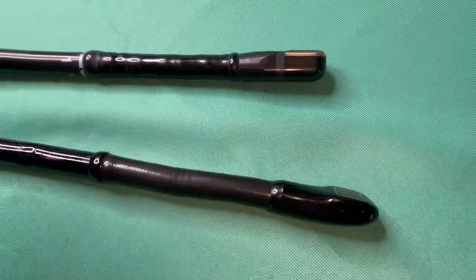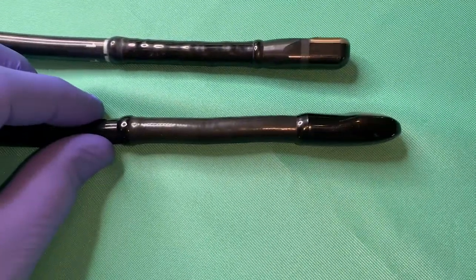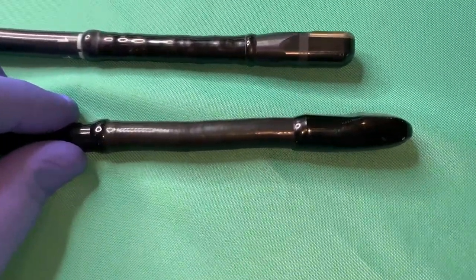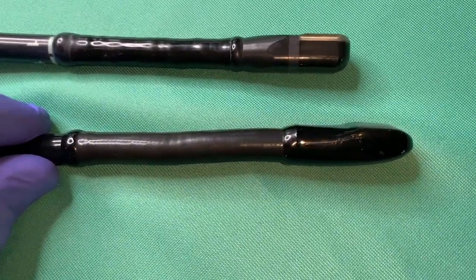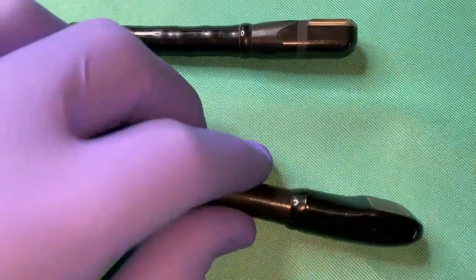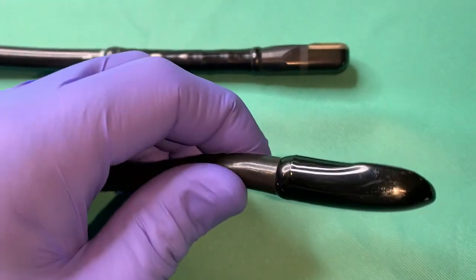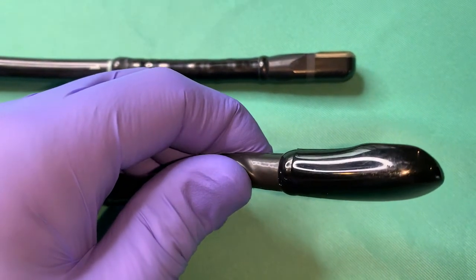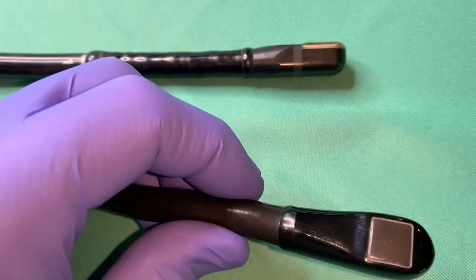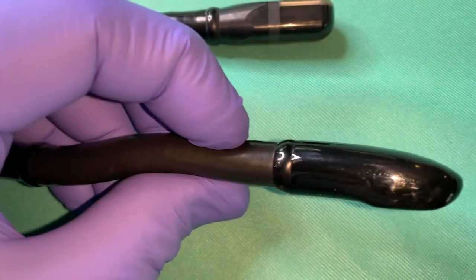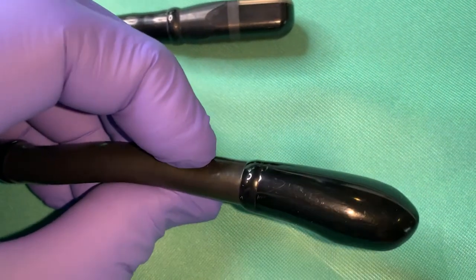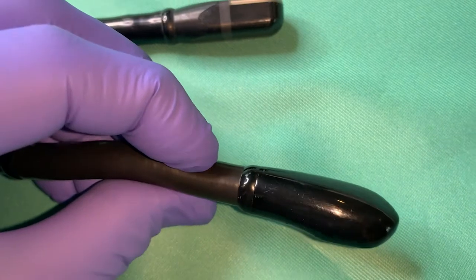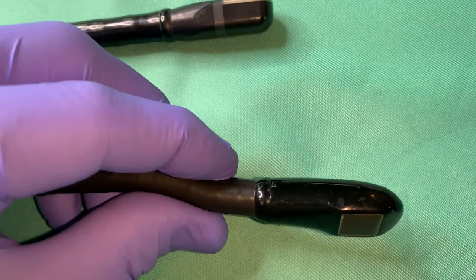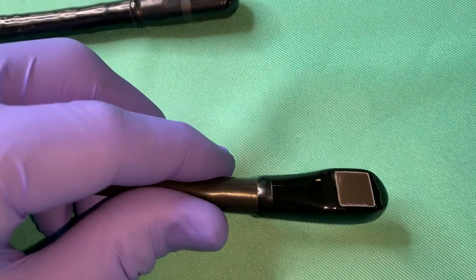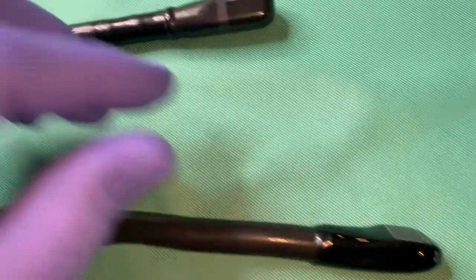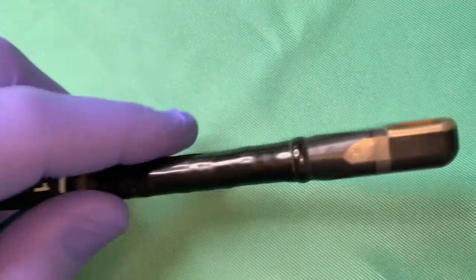The distal tip houses extremely sensitive electronics, similar to those within a flexible endoscope. The distal tip is typically a two-piece clamshell design, but some models consist of up to 4 different components. Traumatic impacts have the potential to break the adhesive bonds between the various sections. Make sure to inspect the distal tip under magnification, examining the seams between each section.